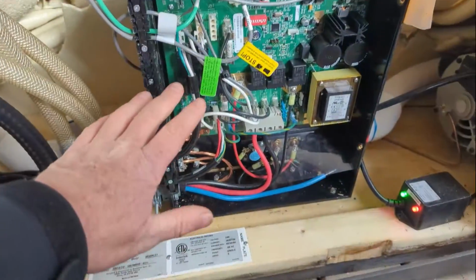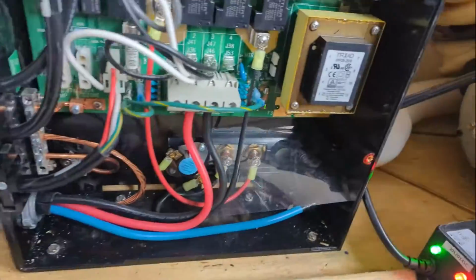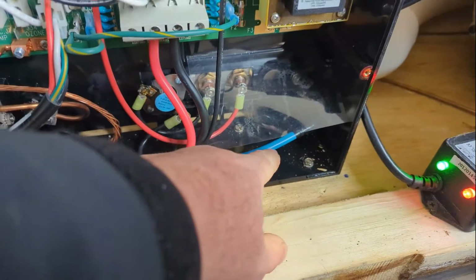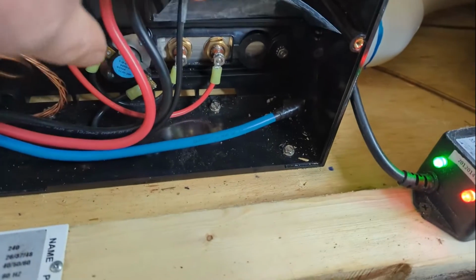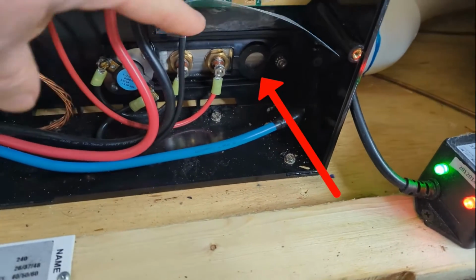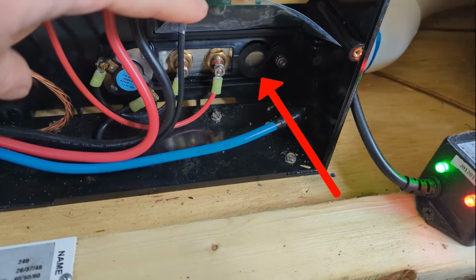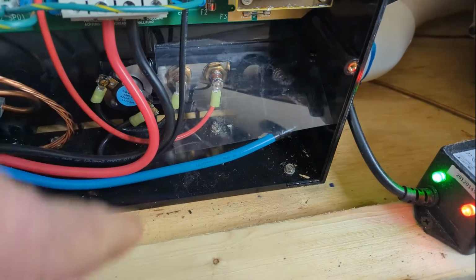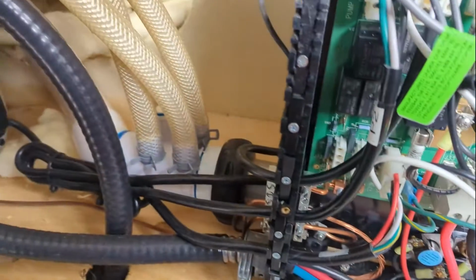So it's probably going to be a flow switch. Now it depends on what year you have, sometimes there are pressure switches like this here, where the heat tube is, normally there's a pressure switch right there. But this one doesn't have a pressure switch, and I can't see if there's a flow switch.